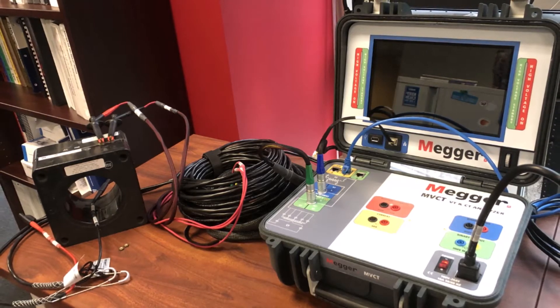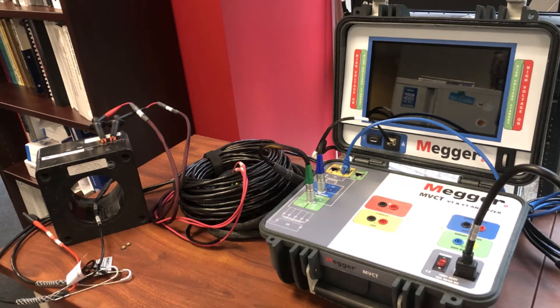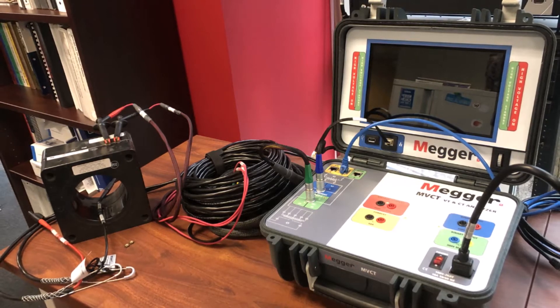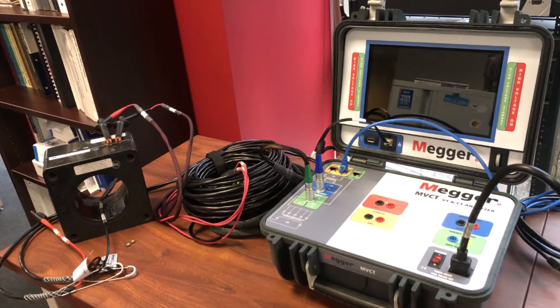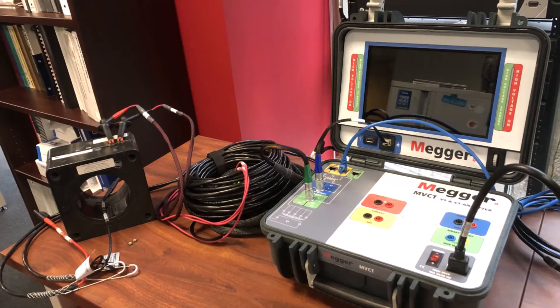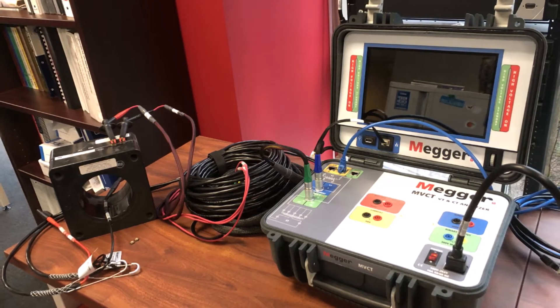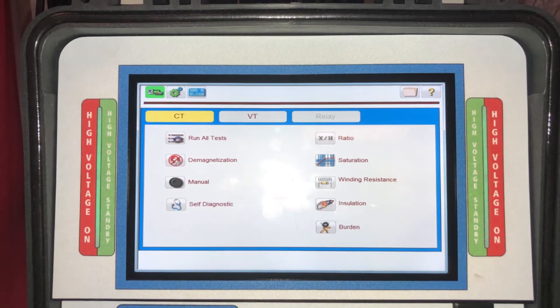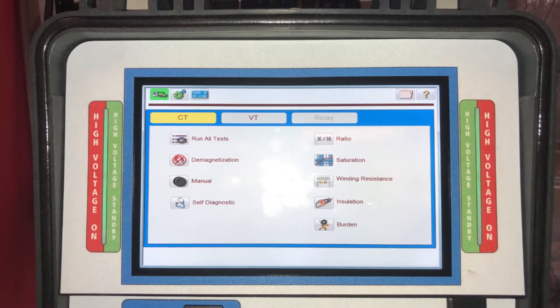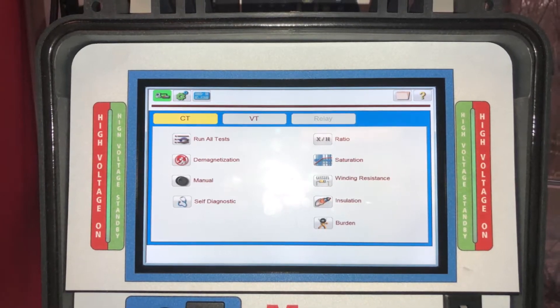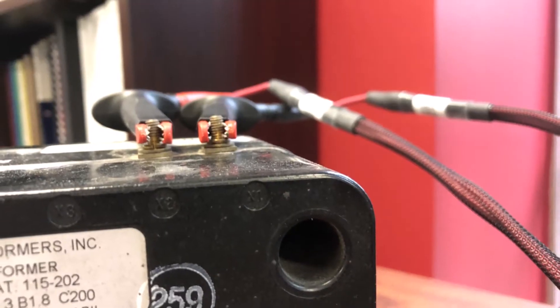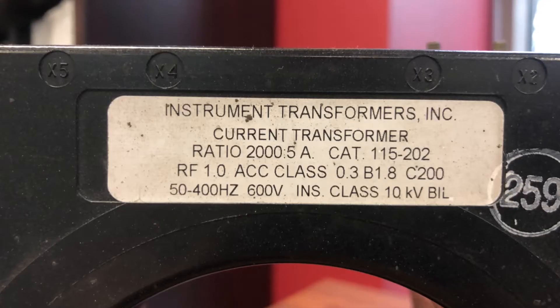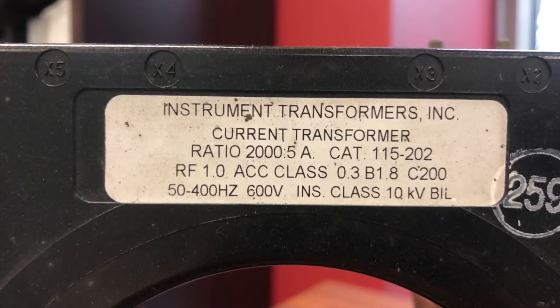Here is the connection setup of the MVCT testing set and current transformer. The set is connected to the Windows-based Megger PowerDB interface software via Ethernet. All testing is run from this interface for the purpose of this presentation, but the set can be ordered with a touchscreen HMI for ease of use, especially when out in the field applications. The CT under testing is a GE-ITE 2000 to 5 ratio, single tap NC accuracy class C200 600 volt insulation.